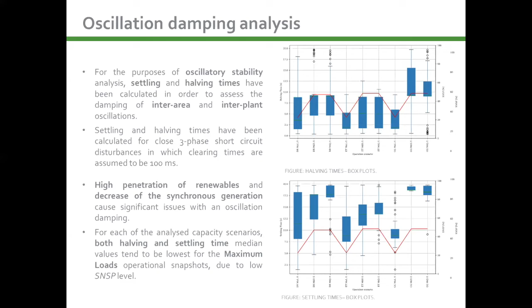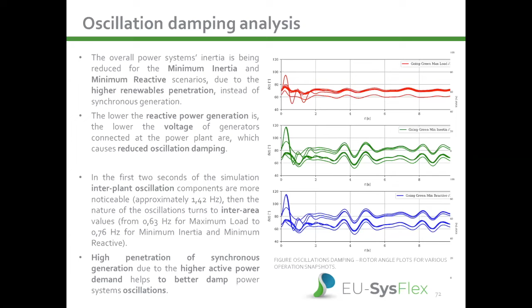Overall, the power system's inertia is being reduced for the minimum inertia and minimum reactive scenarios due to higher renewables penetration instead of synchronous generation, as you can see in the presented figures showing rotor angle plots for various operational snapshots, sample ones. The lower the reactive power generation in the system is, the lower the local voltage of generators connected at the power plants are, which causes reduced oscillation damping in the system. In general, high penetration of synchronous generation due to the higher active power demand helps the system to better damp power system oscillations.